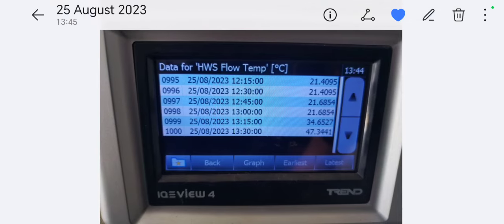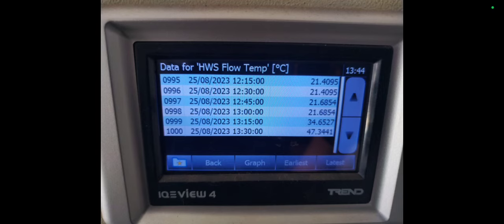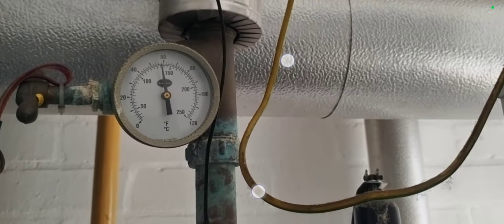And I need to go back and check the capacitor, which is connected to the fan. And then possibly it could be the PCB. But I need to go and check to see what the problem is with this particular unit. It's working now, but I want to see what's causing it to behave in an intermittent way. Here I am checking. So here it is, making and breaking. That last video was the unit making and breaking, the air pressure switch. And then this is the record of the hot water. Lo and behold, now we have it hot.